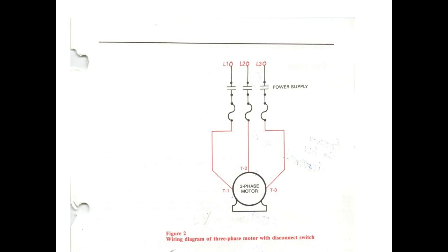By the way, one of the things you're going to do is single phase the motor. Over here we either got 3-phase or single phase, there's no such thing as 2-phase. If you lose one of your power lines on a 3-phase system, you get single phase, because the other one acts like a return. Y'all understand that? So we don't have 2-phase.